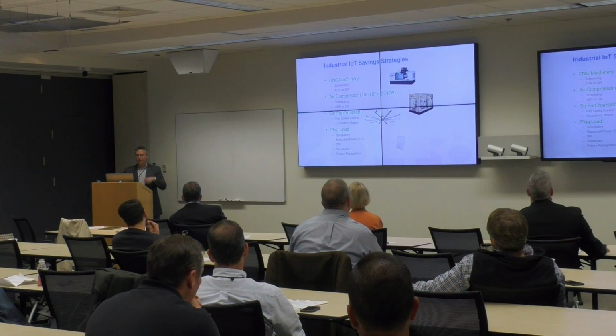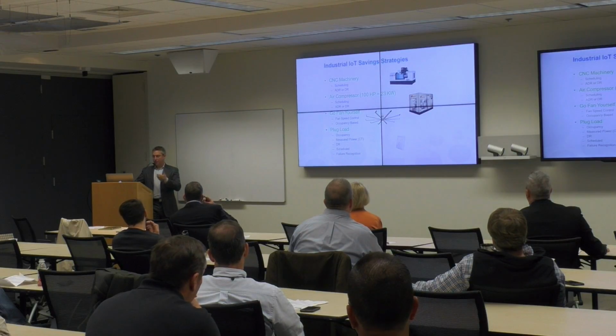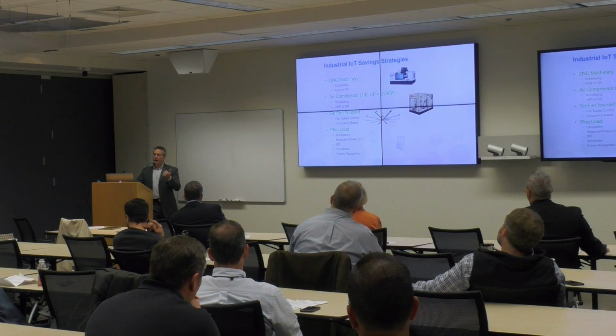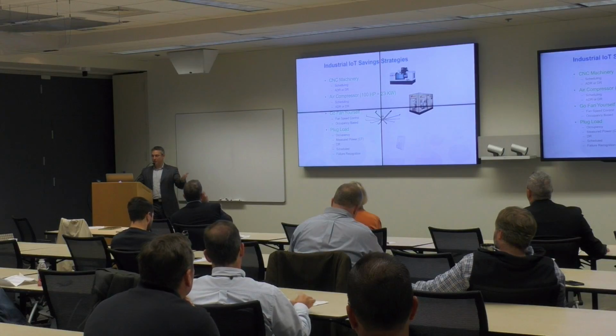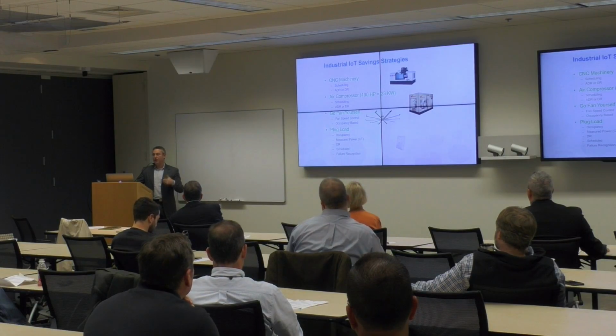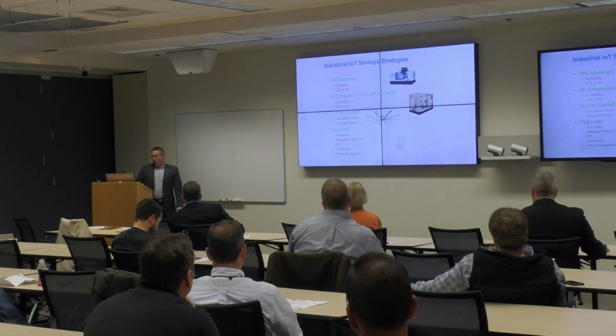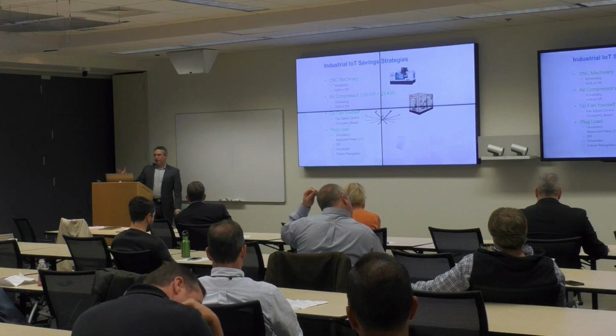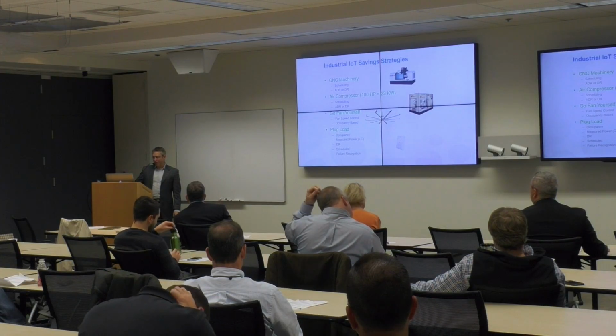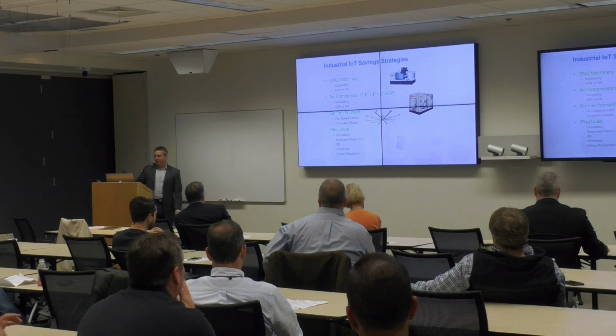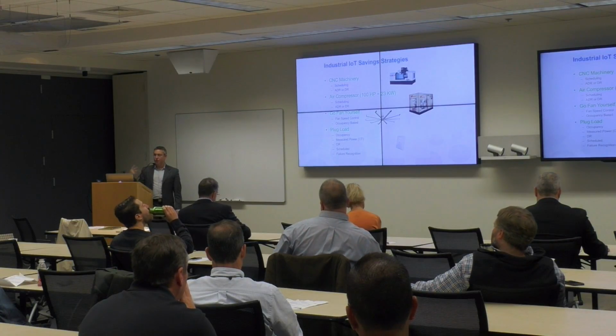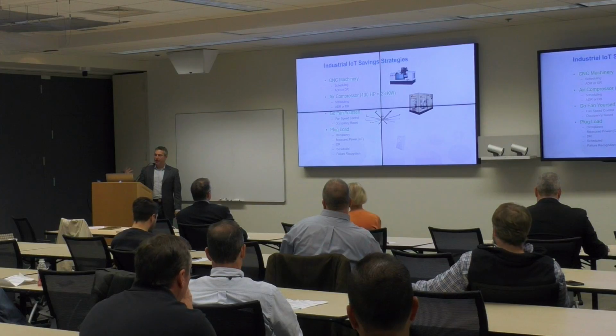I'll give a bit more detail on some examples. Let's talk about fans, because that's a really easy one. If you've got temperature sensors, either in the lights or separately since they're wireless in the space, you can use that to dynamically control fan speed. You can also use that for a demand response event. On plug load, you can use it in the extreme case for window air conditioning units, for demand response events, and to monitor and create energy savings, awareness, and reporting.